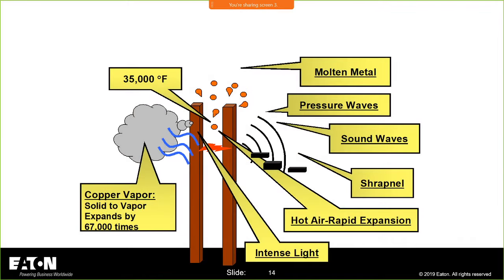So that video really demonstrates the third electrical hazard, which is the blast. There's force associated with this. The temperature at that source was upwards of 35,000 degrees Fahrenheit. We vaporized copper, the plastic and any aluminum that was in there. Anybody in and around that area, when you shock somebody and startle them, it's that initial breath you breathe in that causes damage inside your lungs. But that is a violent event and demonstrates a lot of what an arc flash event is.